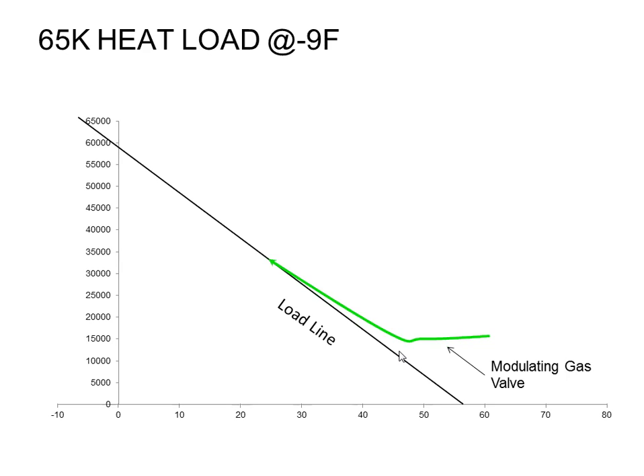then he's going to say, gosh, I ramped it down to 40%, and you still have too warm of a space. I'm going to actually have to go ahead and shut off. And he will shut the gas valve off until the space cools down near 69 degrees, then he'll turn back on again and ramp his gas valve up and down to maintain 69. So if you change the set point, that would be another time.